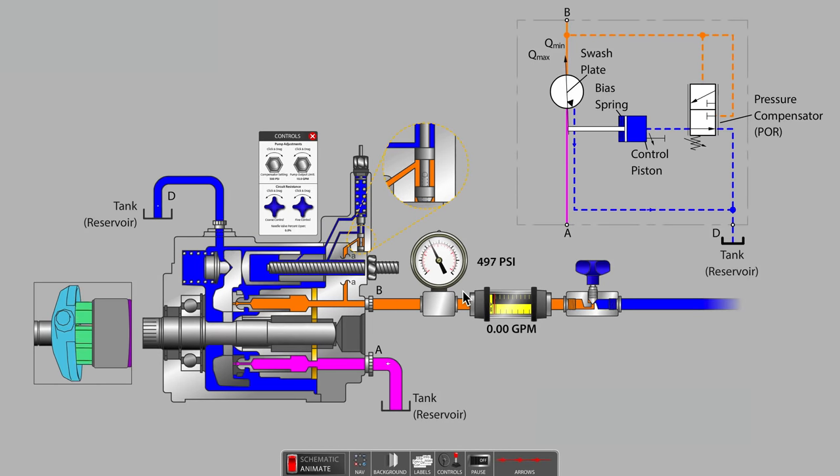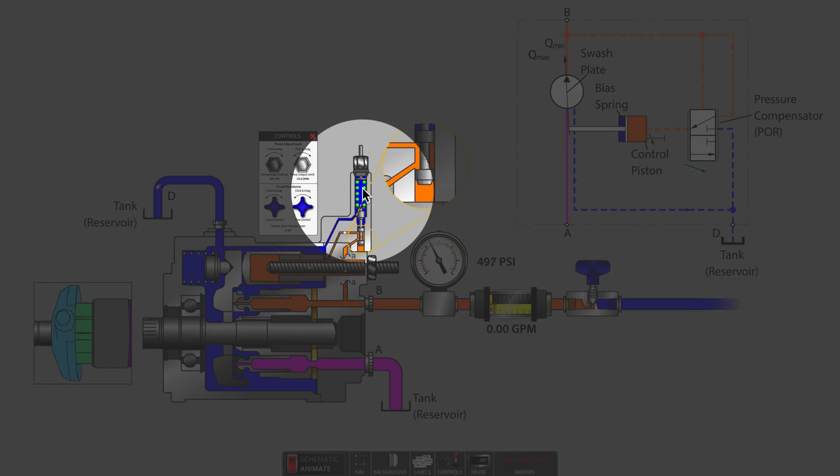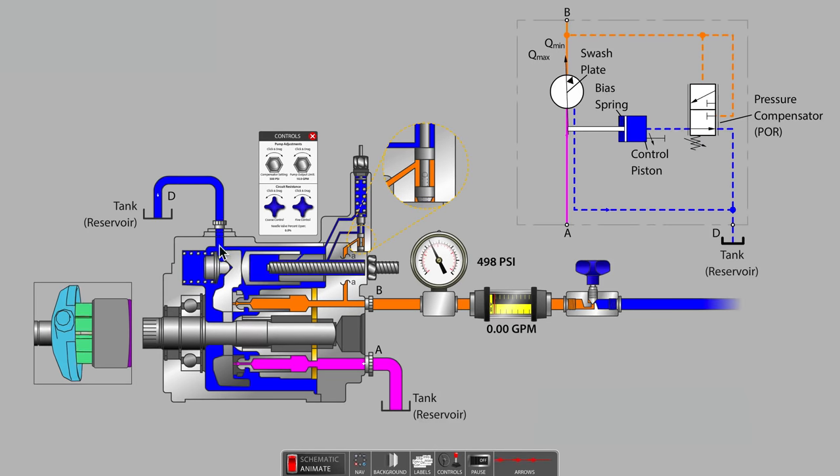In every piston pump, some fluid is leaking internally between close fitting parts. When the swashplate is perfectly vertical, this leakage causes the system pressure to drop slightly. The spring inside the pressure compensator pushes the spool downward to the closed position. This allows the bias spring to push the swashplate back towards the maximum angle, which would increase the stroke length of the individual pumping pistons.